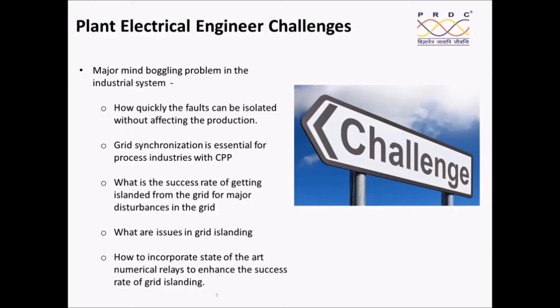And the success rate of islanding from the grid for a major disturbance in the grid, that is, whenever a disturbance occurs in the grid, how I am able to get isolated, is very, very important. And what are the issues in grid islanding? One thing is, I can have a very sensitive setting so that whenever there is any disturbance in the grid, I can get isolated.